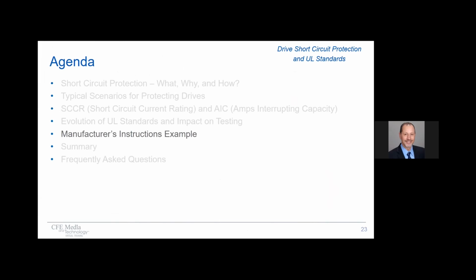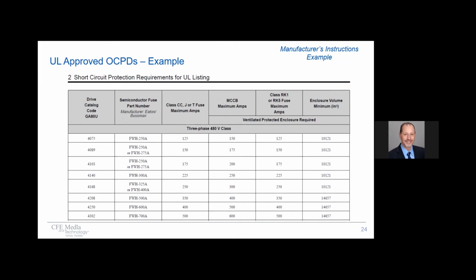As I just mentioned a moment ago, we will now look at an example of manufacturer's instructions. So let's do that. This is such an example, but each drive supplier has their own way of organizing data and footnoting. This is just one example. As you can see in this example, there are multiple choices for protective devices. First, notice in this case that fuses can be used without restriction, including the case of a standalone installation. In other words, no supplemental enclosure.